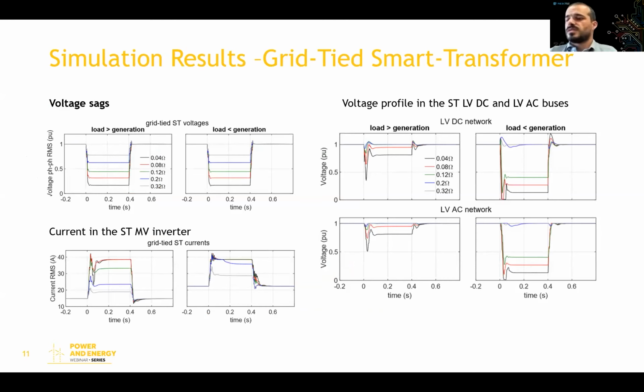So the results are as follows. For the grid-tied smart transformer, on the left we have the voltage sag profiles that were simulated for each fault impedance and for the net generation and net load scenarios. As a result, we can see that the current limits are successfully preserved. And on the right side, we can see what happens in the distribution network in order to preserve such limits.